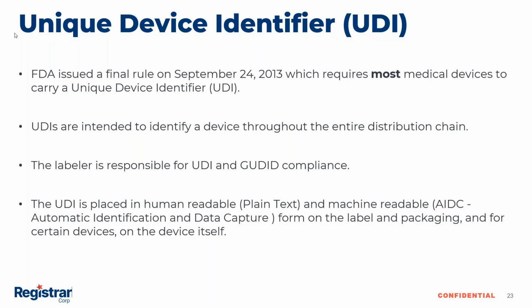Who is required to comply with UDI? It would be the labeler. The UDI must be placed on packaging and labels in both plain text and human and machine readable form.